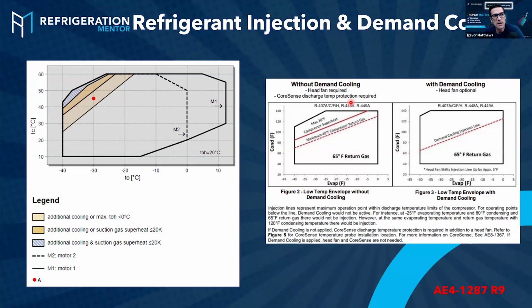So before I started, the big thing is that the CoreSense has the motor overload protector in it. So instead of having the INT69 or the Kriwan module, like all the manufacturers were using at one time, they built their own. So if you had that temperature probe in there, you only need to use a head cooling fan, so it would trip off the compressor. So it would nail you because you're running hotter. And on these, the demand cooling would not be active. For instance, minus 25 evaporating, 80 Fahrenheit condensing, 65 return gas temperature, there would not be any injection. So that's over on this side.